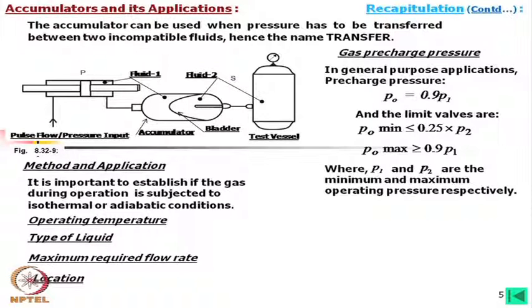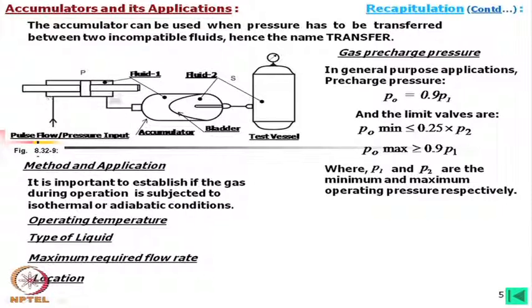Another application is fluid transfer. For example, this can be used for testing a vessel with water — inside the bladder we can put water, and on the other side hydraulic oil, and then by a reciprocating actuator (equal rod on both sides) we can generate a pulsating load. This pulsating load is transferred through the accumulator to the test vessel, and the vessel is tested for fatigue load.